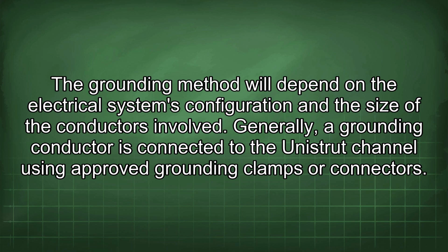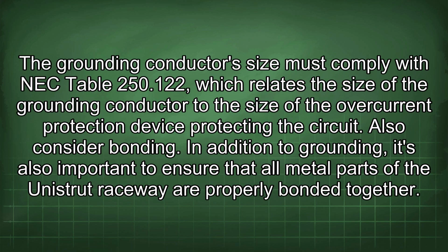Generally, a grounding conductor is connected to the Unistrut channel using approved grounding clamps or connectors. The grounding conductor size must comply with NEC Table 250.122, which relates the size of the grounding conductor to the size of the overcurrent protection device protecting the circuit.